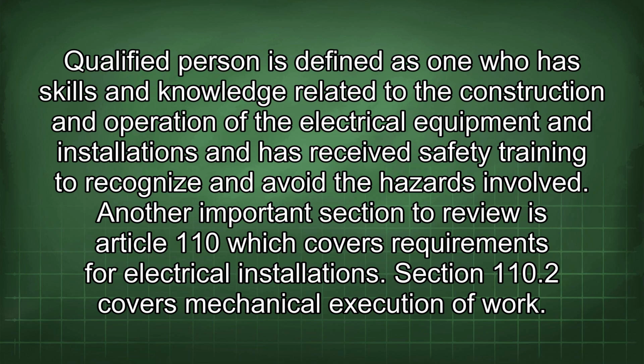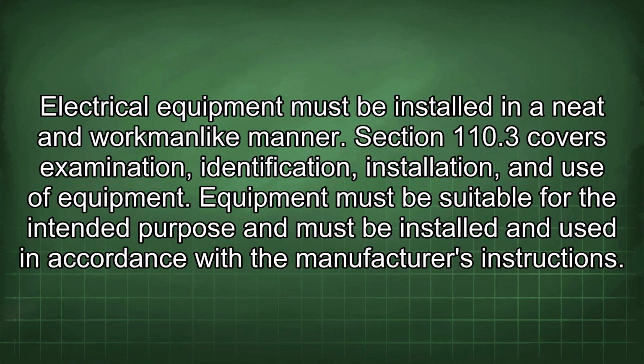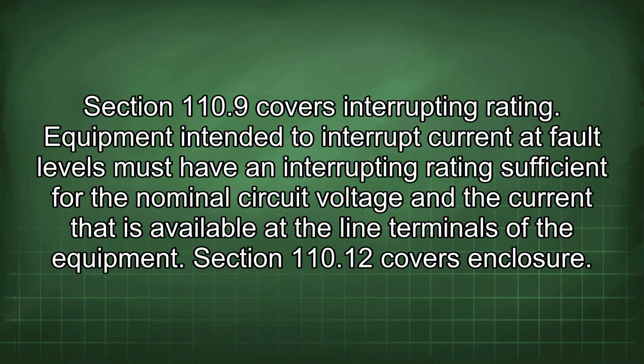Section 110.2 covers mechanical execution of work. Electrical equipment must be installed in a neat and workmanlike manner. Section 110.3 covers examination, identification, installation, and use of equipment. Equipment must be suitable for the intended purpose and must be installed and used in accordance with the manufacturer's instructions. Section 110.9 covers interrupting rating. Equipment intended to interrupt current at fault levels must have an interrupting rating sufficient for the nominal circuit voltage and the current that is available at the line terminals of the equipment.